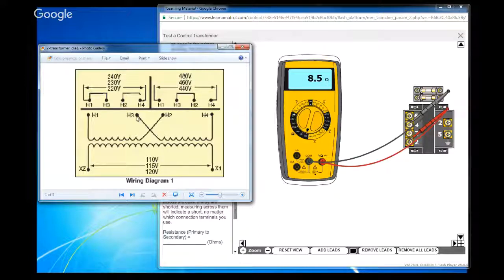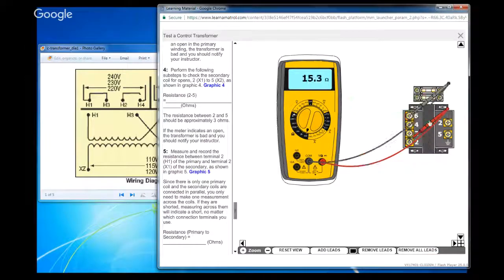Okay, now let's do the opposite check here, H3 to H4. So we're going to come over here, and I'll see that I have 8.8 ohms, which is pretty close. If you have a point, I would say a 0.5 ohm variance, don't worry about it. Okay, and we should also check the ground. I actually have a bad transformer we're going to look at, which will give us a clearer view of what a real world transformer is, but we were looking for a resistance balance in these coils.